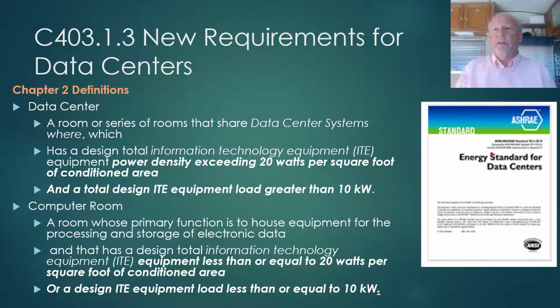A data center is defined in the code as a room or series of rooms that share data center systems where they have a power density exceeding 20 watts per square foot of conditioned area and a total design ITE equipment load greater than 10 kW. So if that fits your specific room or series of rooms, it is defined as a data center and the HVAC must comply with ASHRAE 90.4.